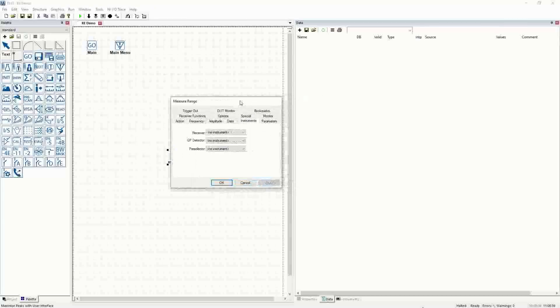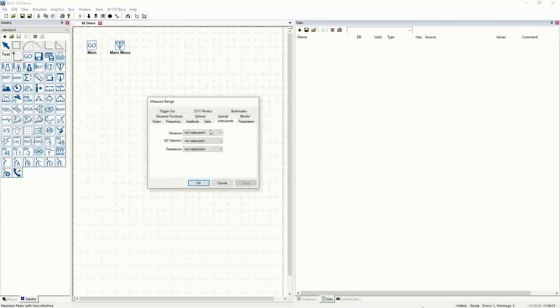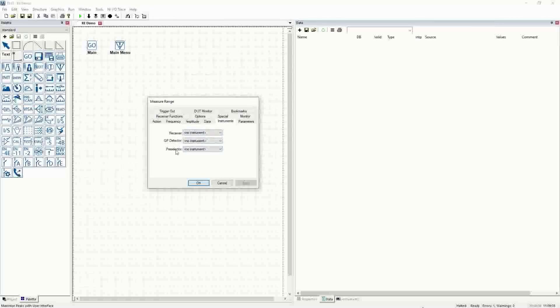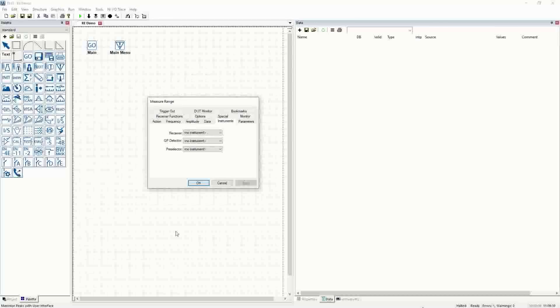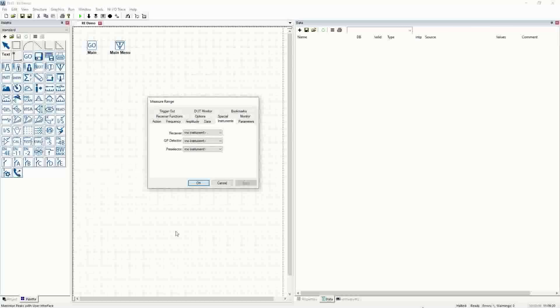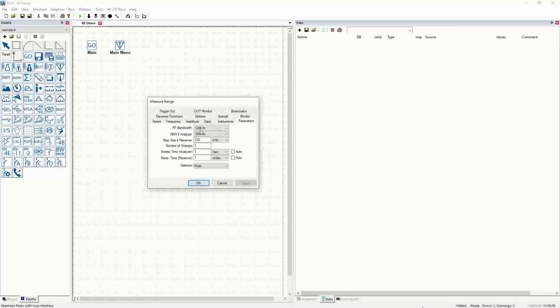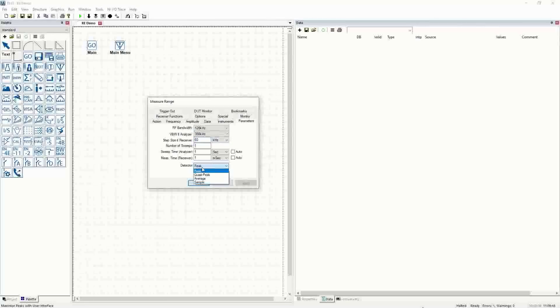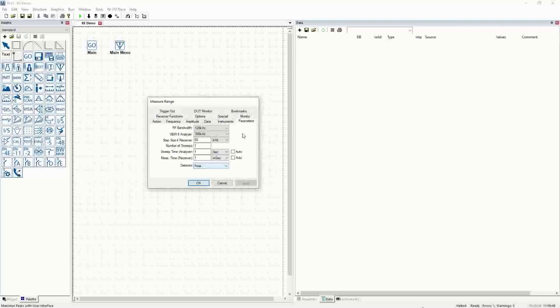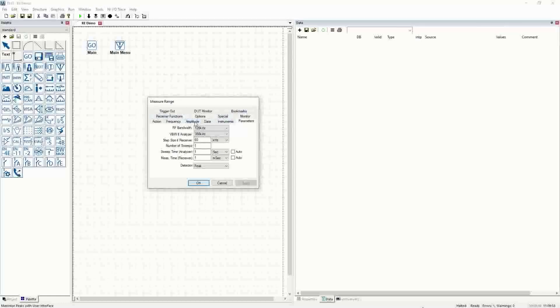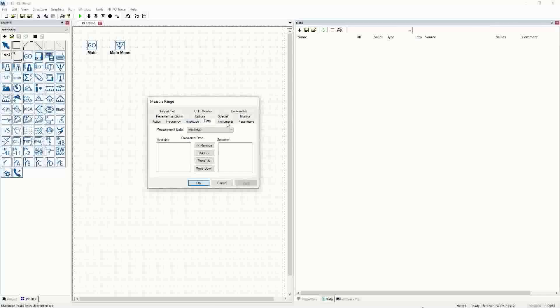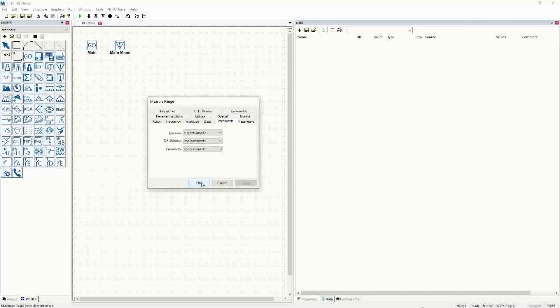You'll notice in this profile there's space for three instruments: a receiver, a quasi-peak detector, and a pre-selector. That is in case you have off-board equipment. A long time ago, HP had a flagship receiver that was the 8566B, and it had secondary pieces of equipment that were quasi-peak detectors and pre-selectors, and they were separate. Now, modern receivers and spectrum analyzers have these things built in, so you would only put an instrument in the receiver area. Then there's the test parameters - you set up your bandwidth, step size if it's a receiver, which detector you're going to be looking at. In this case, we're using a spectrum analyzer, it's just going to be a peak sweep. We really need to add to this a data element and an instrument.